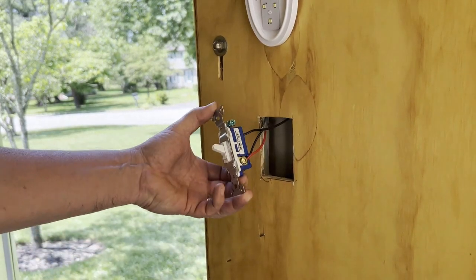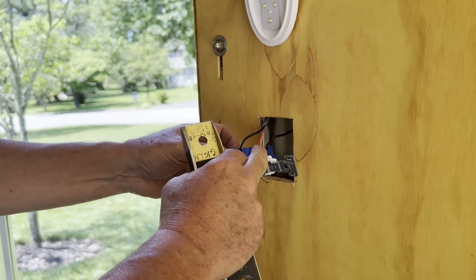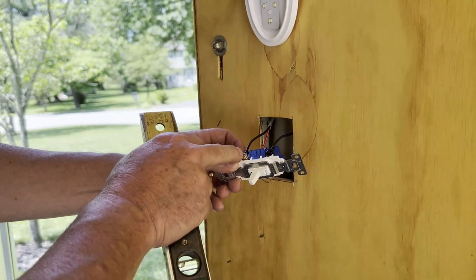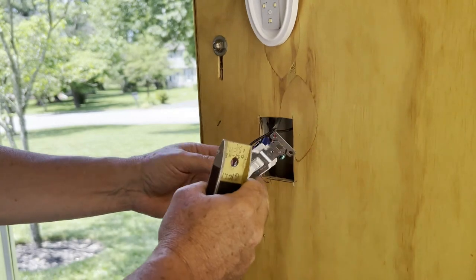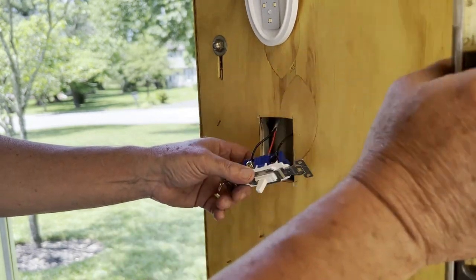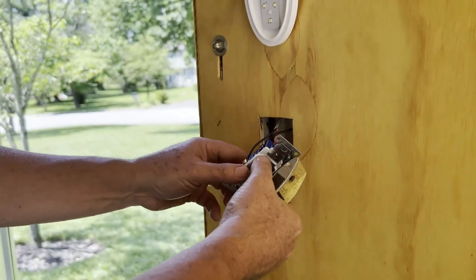So the switch is wired now, and just to recap: this black screw is the common screw that the switch will always be connected to. When you flick the switch, you'll either put the contact on this screw or this screw. These two are called the travelers, and they will go on the corresponding toggles on the other three-way switch. The black screw on the other three-way switch will go to the light. That's how three-way switches work.